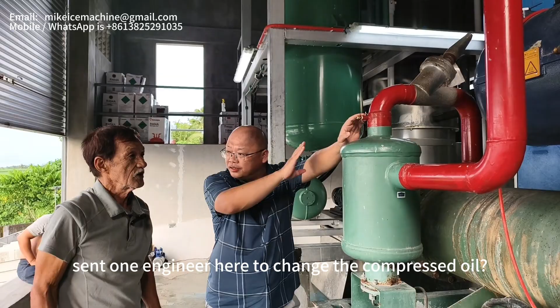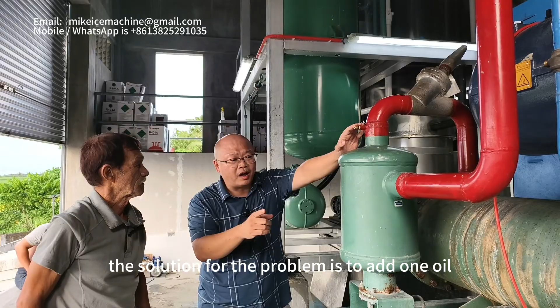We do everything. We clean all the condenser, but still nothing. I remember you said CBFI sent one engineer here to check what the problem is, but he never solved the problem. Of course, the problem can never be solved. The solution for the problem is to add one oil cooler or change the system into R404A, because R404A has a lower discharge temperature.